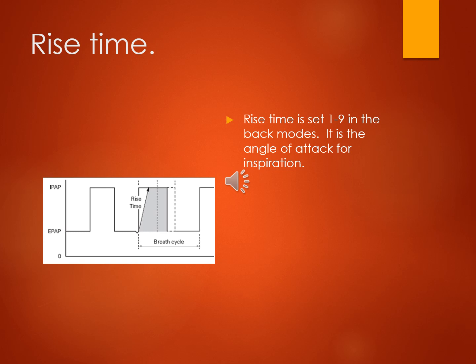Now, here's the other side. If you had a rise time of 9, it's going to make that angle of attack go further to the right. So the bottom left part is the beginning of inspiration, and it'll go all the way to the top right before it actually meets its peak pressure or its pressure control setting. So that could literally cut that volume in half.